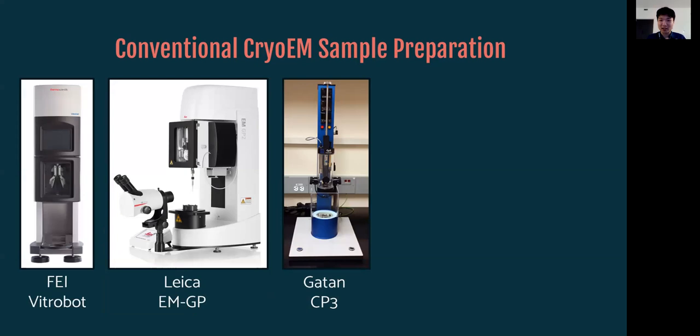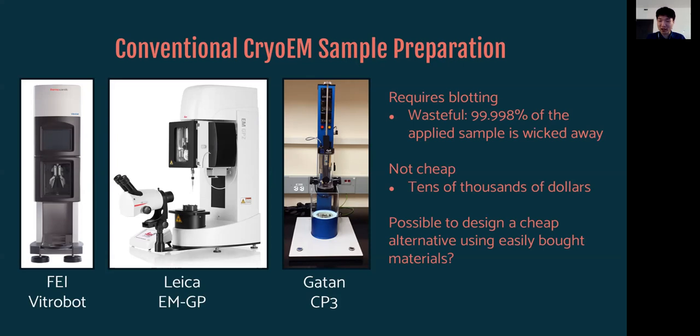Many conventional sample preparation devices are being used currently. So these are the more popular ones such as the VitroBot, Leica GP and Gatan CP3. So all these are good workhorses that utilize the blotting technology and have been used for many cryo-EM papers and many labs around the world. So they work really well and produce consistent grids. One of the issues that they have is that it is quite wasteful. So all these devices require blotting, as I mentioned earlier, which you slap a piece of filter paper and wick away a lot of the sample. And actually 99.998% of the sample is wicked away by this technology. So you actually lose a lot of protein. Second of all, these devices are not cheap. They cost tens of thousands of dollars.